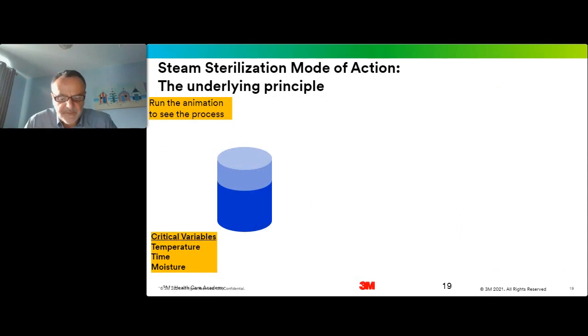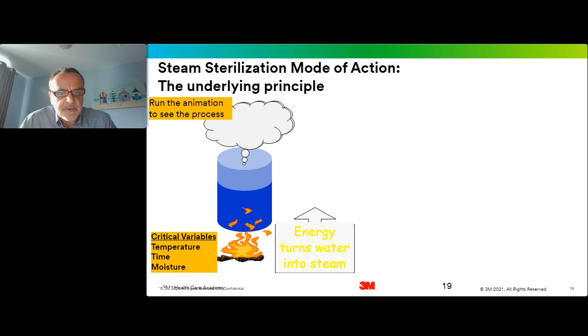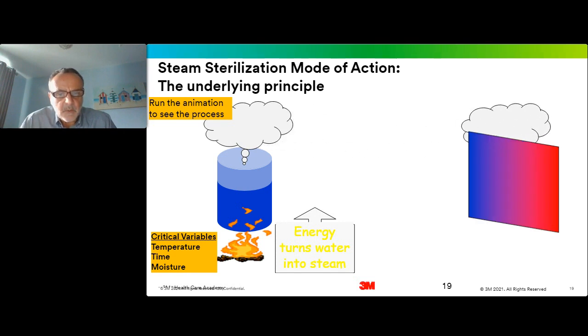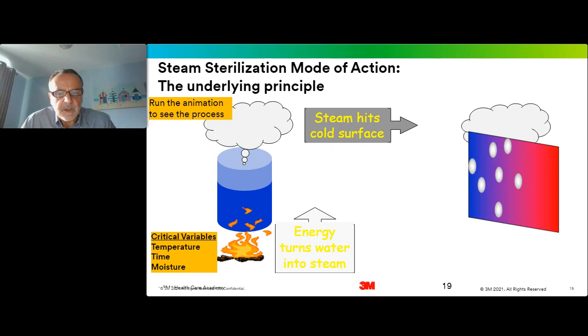So I think let's first have a look at how steam is generated, transported to the sterilizer, and then impacts on the load inside the sterilizer. Obviously, if we add heat to water in our boiler, it will begin to produce steam. And then that steam is transferred into the steriliser, where it will condense on the surface of our load items.